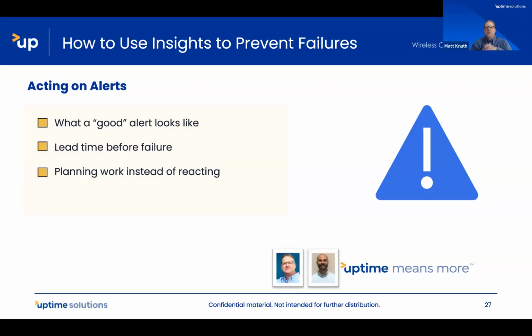I like the framework of actionable, investigable, relevant, and unique. I could give a one day seminar on setting alarms, or on not setting alarms. But the quick and dirty is: in a constant speed, constant load system, like a fixed speed fan, the vibration or temperature should always be roughly the same. If it changes, it's highly likely a fault is occurring, and we're going to look into that.